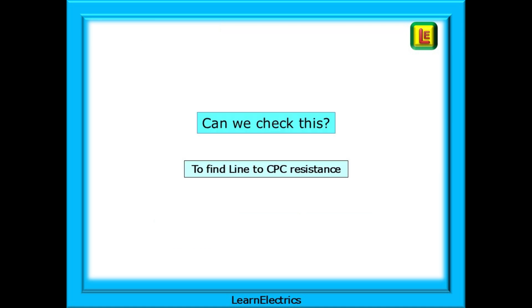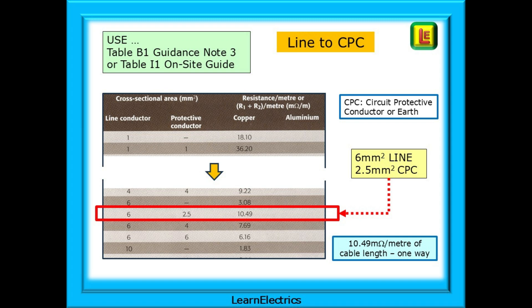But can we check this? How do we know that these numbers are correct? We can begin with checking the line to CPC resistance in the tables. These tables are very easy to use and I do recommend that you practice using them — they will prove so useful in your career. We can use either table B1 in Guidance Note 3 or table I1 in the On-Site Guide; it's the same table, the same data. We are using 6x2.5 twin and earth, so begin by looking down the line conductor column — the leftmost column — and find the block for 6mm conductors. Now find the protective conductor or CPC size in the second column, which is 2.5 square millimetres. The third column will give you the combined resistance of 6x2.5 copper cable, and this is 10.49 milliohms per metre length measured just one way.